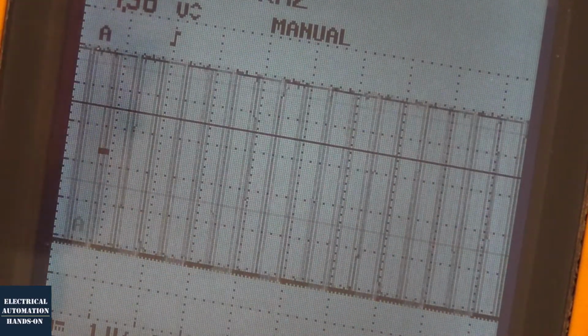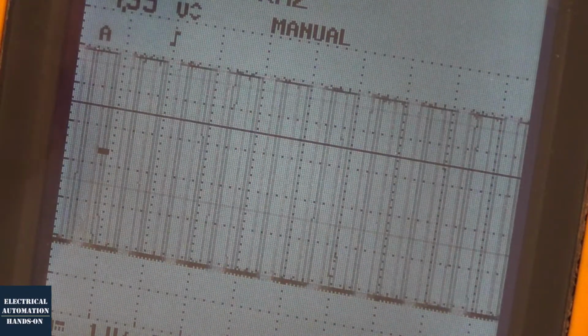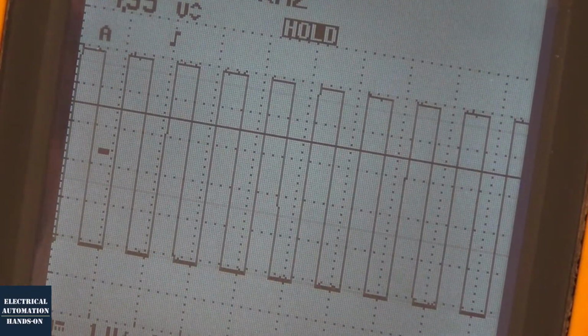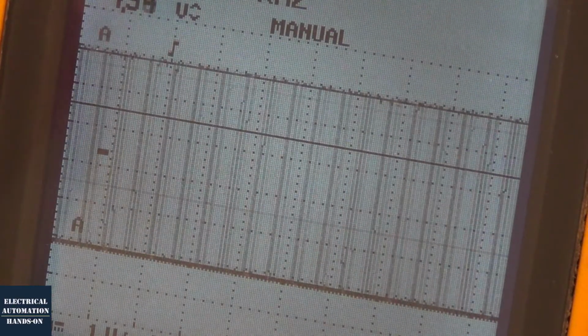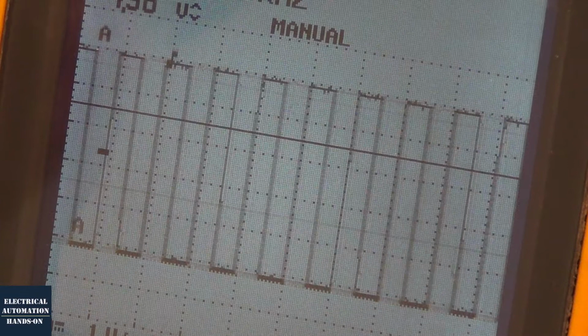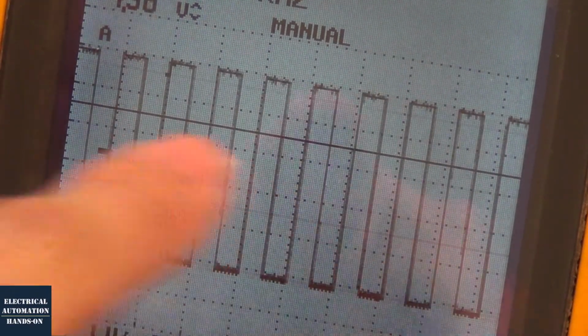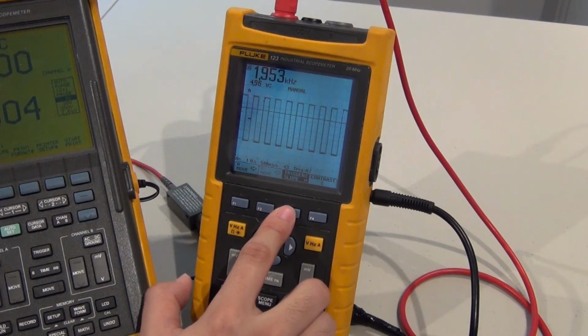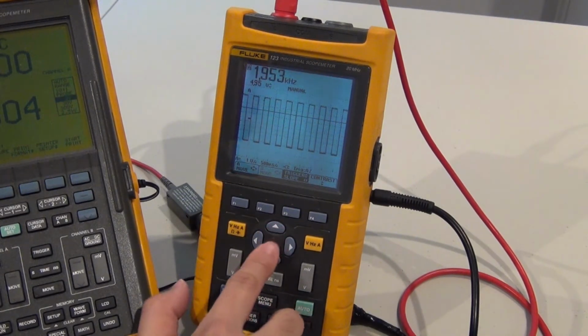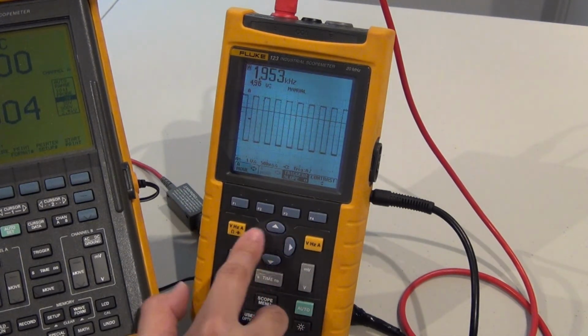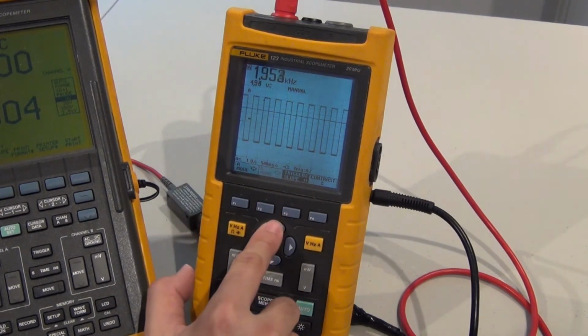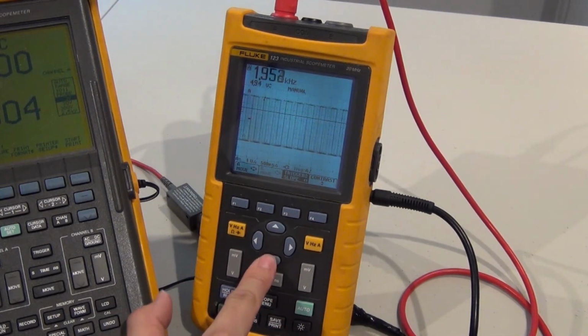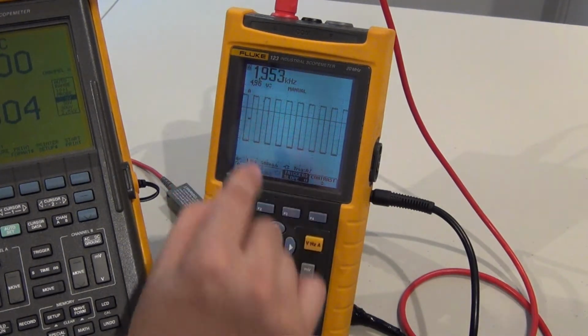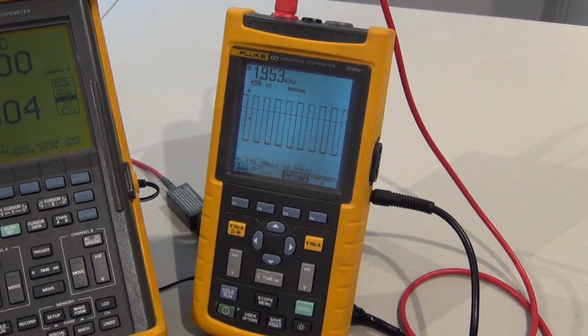So basically, it's really hard to check the signal here unless you hit this hold button and hold the signal. But the best way is to use the trigger signal. Move this trigger signal, it will detect the edge and hold this signal. To adjust this trigger position, we can hit F3, enable this trigger slope, and then press up and down, left and right. You can move up or down to find a position that allows these small curves to hold your signal. Alright, this is the Fluke 123 brief demonstration.